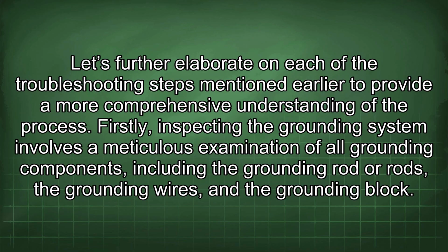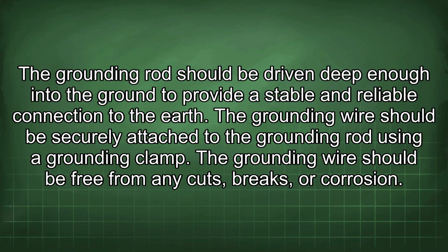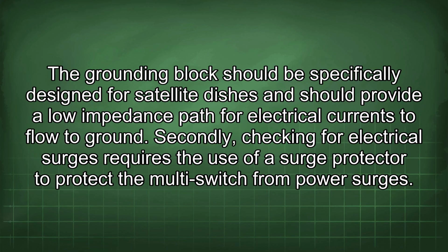Let's further elaborate on each of the troubleshooting steps mentioned earlier to provide a more comprehensive understanding of the process. Firstly, inspecting the grounding system involves a meticulous examination of all grounding components, including the grounding rod or rods, the grounding wires, and the grounding block. The grounding rod should be driven deep enough into the ground to provide a stable and reliable connection to the earth. The grounding wire should be securely attached to the grounding rod using a grounding clamp. The grounding wire should be free from any cuts, breaks, or corrosion. The grounding block should be specifically designed for satellite dishes and should provide a low impedance path for electrical currents to flow to ground.